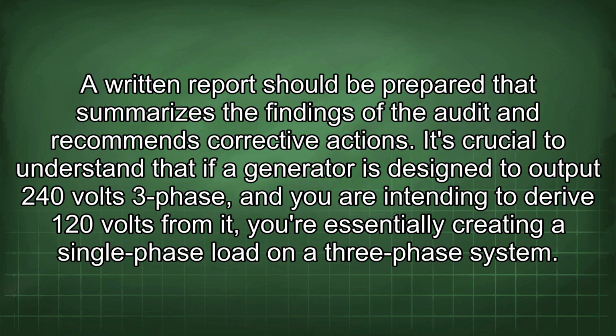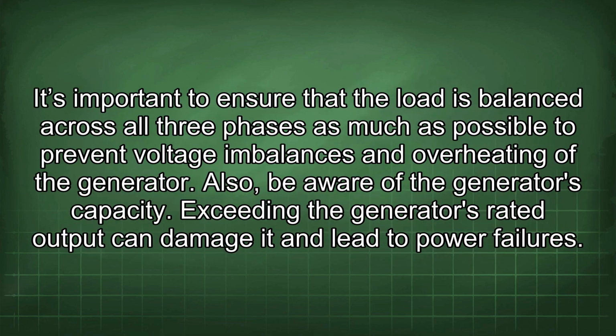It's crucial to understand that if a generator is designed to output 240 volts three-phase and you are intending to derive 120 volts from it, you're essentially creating a single-phase load on a three-phase system. It's important to ensure that the load is balanced across all three phases as much as possible to prevent voltage imbalances and overheating of the generator.